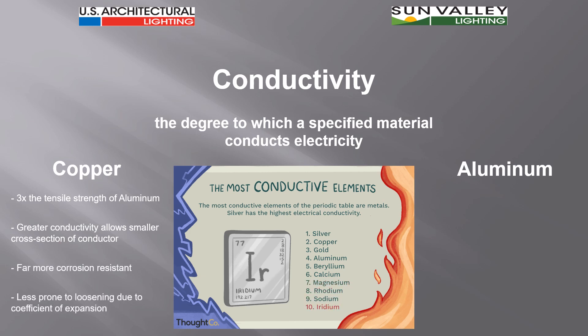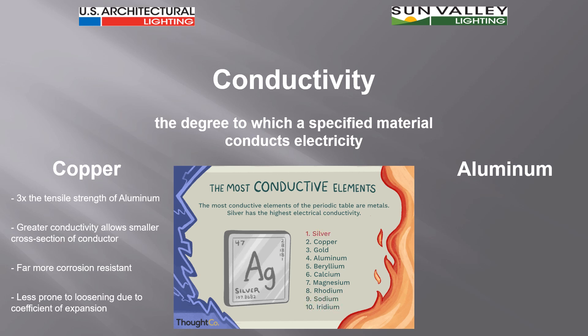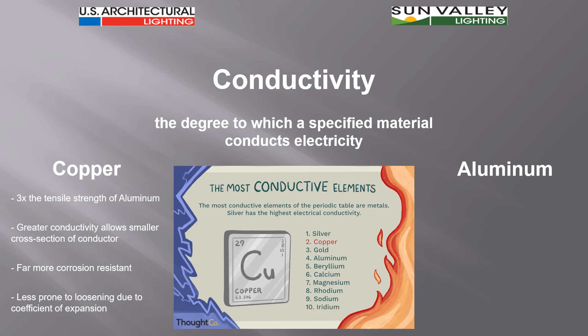Copper is also far more corrosion resistant than aluminum. Copper has been used in roofing for centuries because it doesn't really corrode — it forms a patina surface that adds to rather than subtracts from the copper. Another factor in copper's favor is that it is less prone to loosening due to coefficients of expansion. With aluminum, expansion and contraction at a terminal connection can cause it to work itself loose. That doesn't happen with copper because it has a very low coefficient of expansion, making it a preferred material for wiring and electrical circuits.